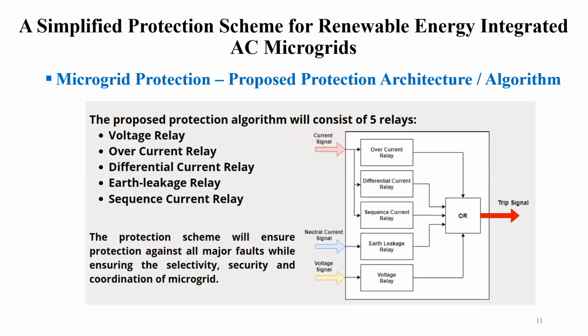What we have proposed here is a protection scheme based on 5 relays, used in such a manner that we have an OR gate, or control logic, between them. These 5 relays are the overcurrent relay, differential relay, sequence relay, voltage relay, and earth leakage relay. We have developed this so that our protection scheme will ensure protection against all major faults while ensuring selectivity, security, and coordination of a microgrid. The inputs for this proposed architecture are the current signal, voltage signal, and the neutral current signal, and by sensing these signals we can generate our trip signals for the operation and coordination of these relays.